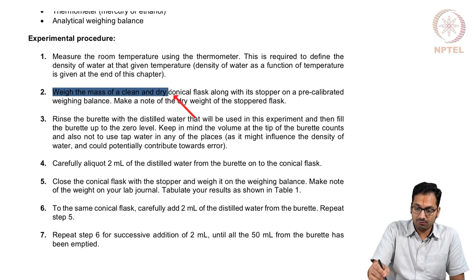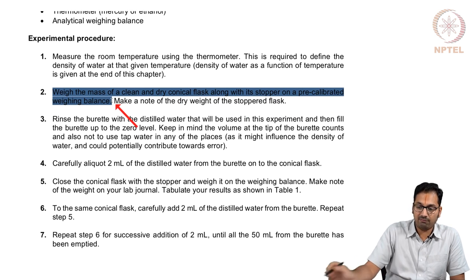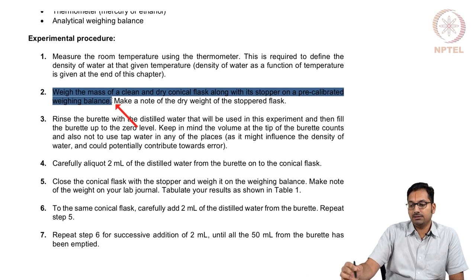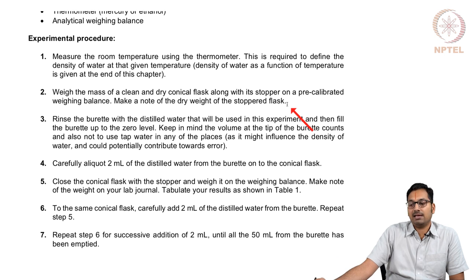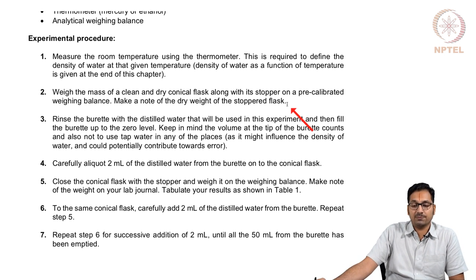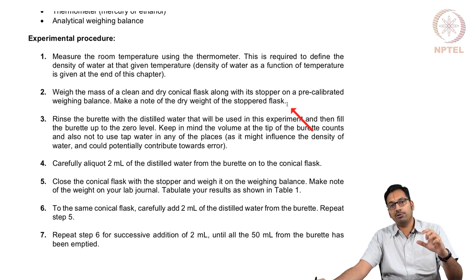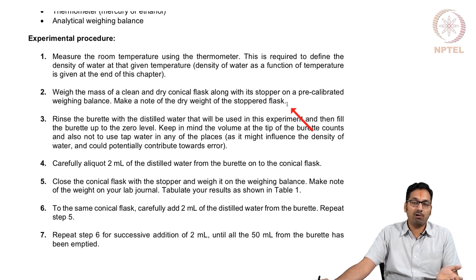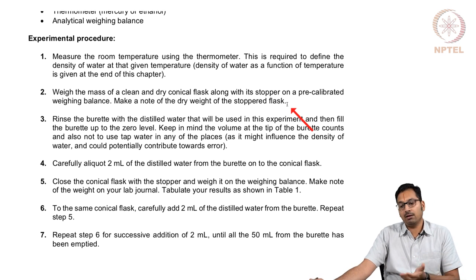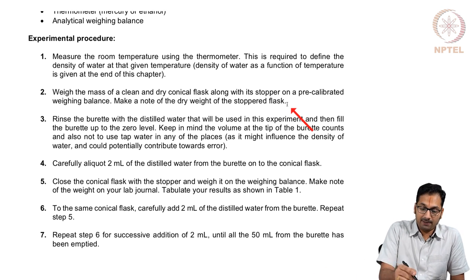The next step is to weigh the mass of the dry conical flask. This is done because this flask is where you will be adding different volumes of water to measure how much comes out. So this helps you understand: if you are aliquoting a certain volume V from the burette and you can measure the same volume by getting the mass and multiplying by density, you will be able to confirm you are doing what you anticipated.